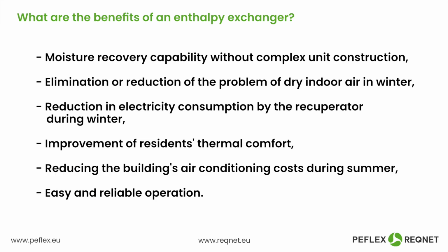What does choosing an enthalpy exchanger give us? The ability to recover moisture without complicating the device's construction, and the elimination, or rather, the reduction of the problem of overly dry air during the winter season. Lower electricity consumption by the heat recovery unit in winter, as well as reduced electricity use by the air conditioner in summer. Improved thermal comfort for building occupants, reduced air conditioning costs in the summer, and simple, trouble-free operation.